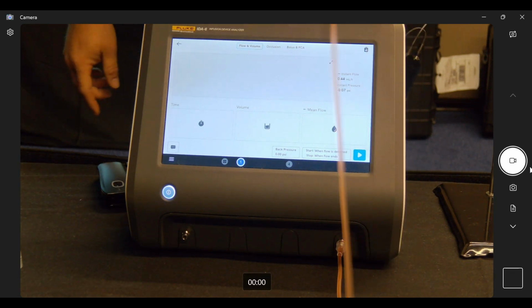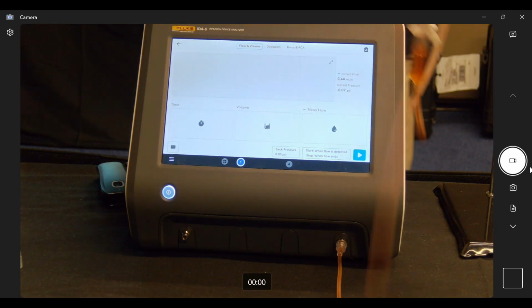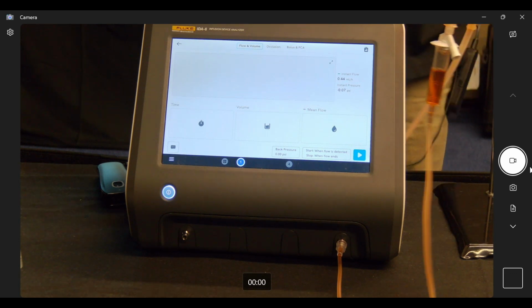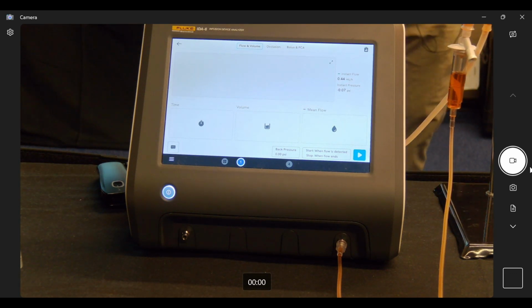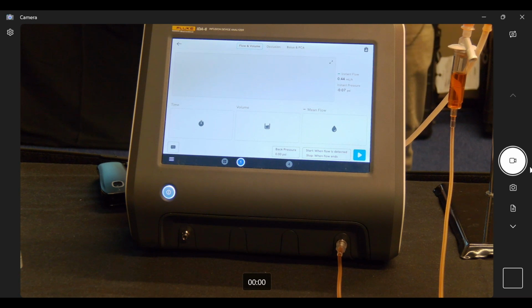But the difference is you notice that my water's not coming out of my bag. This is a really neat phenomenon. This is what we call IntelliPump technology. So what's happening as this is drawing the fluid through the IV pump and into my analyzer, it uses a piston-driven stepper motor. So I have a ceramic piston with a ceramic sleeve in it, and it's pushing that ceramic back and trying to get equilibrium pressure for 0, and it pushes that fluid right back into my bag.